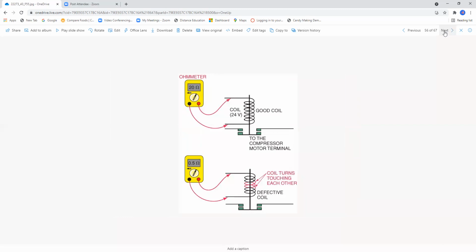Okay, this is utilizing an ohmmeter to check the 4-way valve solenoid coil. Notice, if we have our meter in the ohms position between the 2 coil wire connections, we have 20 ohms. This indicates that we have a good winding on this solenoid coil.